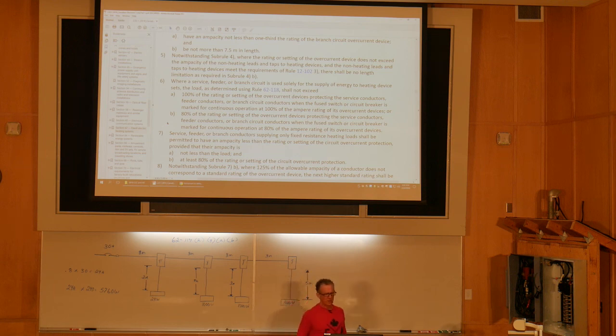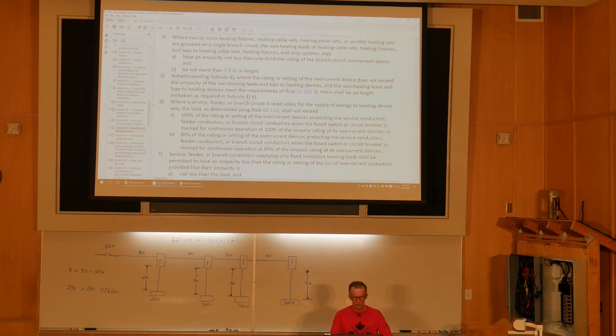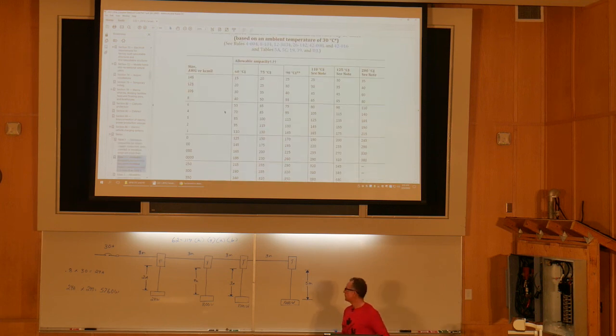Okay, so if we think of it here, we go back not more than 7.5 meters long, so in subrule 4, have an ampacity not less than 1/3 that of the branch circuit overcurrent device. So I've got to be at least 1/3 of that. That's 10 amps. So number 14 is good for that. If we think of it, let's go look at table 2. These would all be 75 degrees. So the termination temperature rule would be in play.